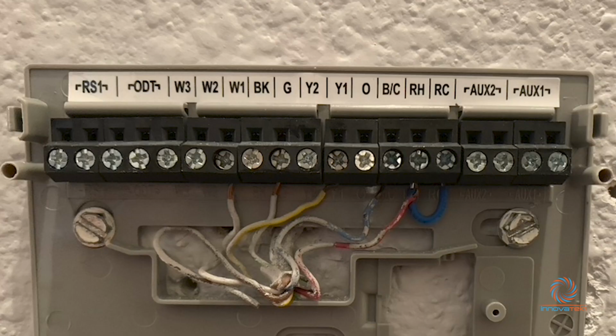Another thing built into this thermostat is what's called the BK terminal. This BK terminal is only compatible with Trane systems that have a variable speed blower motor inside. If you have a Trane system with a variable speed motor, you can take advantage of this terminal as well. If you wire this BK terminal, it tells the thermostat that in case the humidity is too high, go ahead and reduce the fan speed 30% less. This will allow for an even higher dehumidification level before it even starts overcooling.